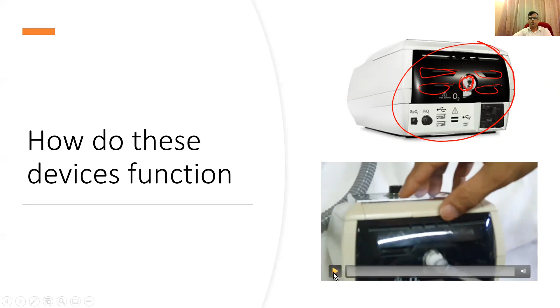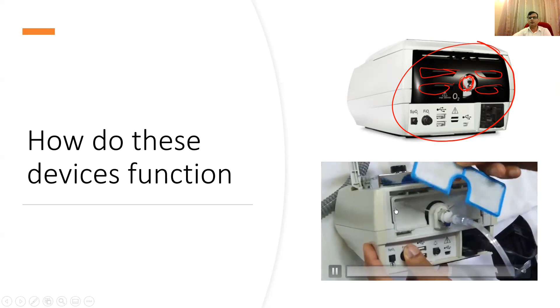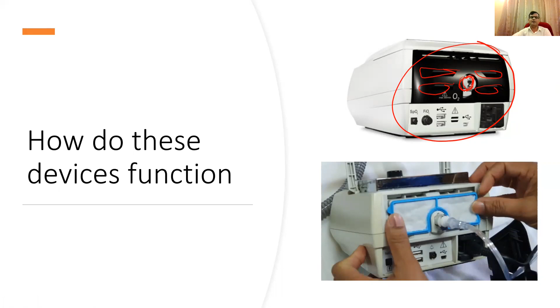Now I'm going to show you what it looks like in a ResMed device. I'm taking this as an example because this is the commonest device. You can see there is an air filter and a big area to entrain air, and there is a small port to connect oxygen into the device. Basically, the machine is functioning using room air to generate these CPAP and BiPAP pressures. This is where the air filter is, and you get a large inlet to entrain air. Basically, these devices function using room air.